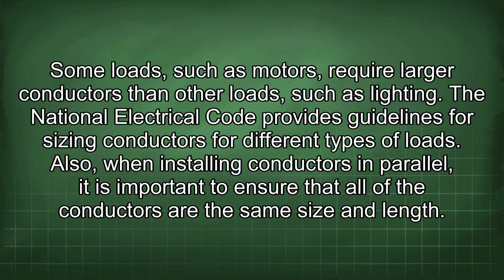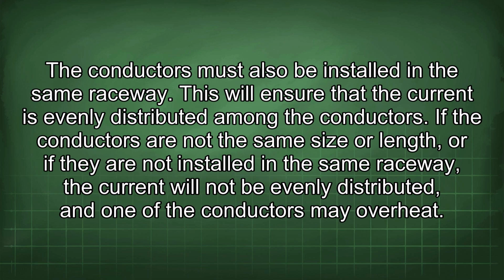Also, when installing conductors in parallel, it is important to ensure that all of the conductors are the same size and length. The conductors must also be installed in the same raceway. This will ensure that the current is evenly distributed among the conductors. If the conductors are not the same size or length, or if they are not installed in the same raceway, the current will not be evenly distributed, and one of the conductors may overheat.